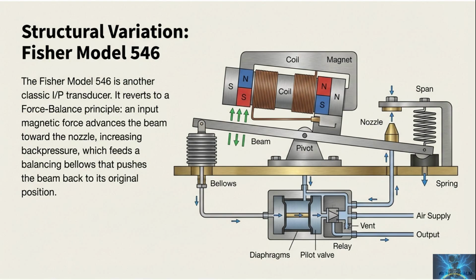Structural variation: Fisher Model 546. The Fisher Model 546 is another classic current-to-pressure transducer, but it uses force balance architecture. Input magnetic force moves a beam toward the nozzle, increasing back pressure. That back pressure feeds a balancing bellows, which pushes the beam back toward its original position. A relay and pilot valve handle the heavy lifting of supply air and venting at the output. Same anatomy, different packaging: sensor, feedback, and amplification.